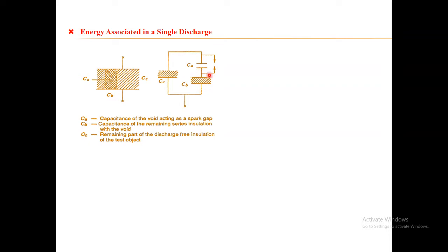Ideally, if you approach this with a simulation kind of circuit to understand the partial discharge activities, one can show the cavity capacitor like a switch. During the normal condition, when the voltage across the cavity is lower than its breakdown voltage value, this switch acts as an open circuit.